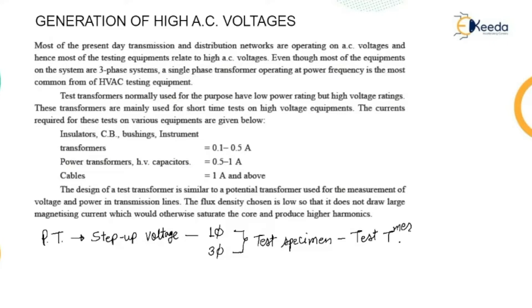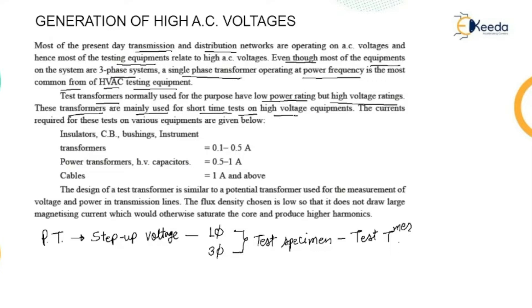Many times, that particular transformer is not sufficient to generate the required level of voltage. This transformer is used for the purpose of transmission and distribution, so equipment on transmission and distribution networks can be tested with it. Even though most equipment is on a three-phase system, a single-phase transformer operating at power frequency is the most common HVAC testing equipment. This test transformer normally has a low power rating but high voltage rating, and is mainly used for short-time tests on high voltage equipment.